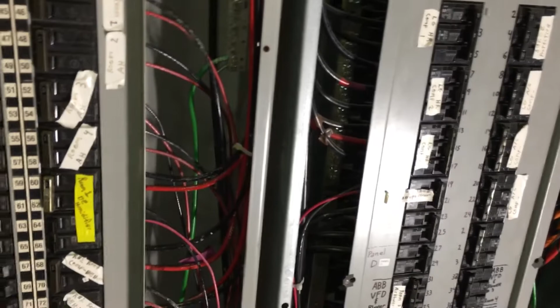If you know the anatomy of how fuses blow, either really slow - they get overamped for a long duration and they just kind of melt and break away, forming a nice little round ball at the end of the wire where it breaks - or you have the actual flash explosion where it's such a big spike going through there that the little filament literally explodes like a flash bulb in a camera. That's a heavy hit surge spike, and you can actually hear these transformers every now and then do the whole building dims down.